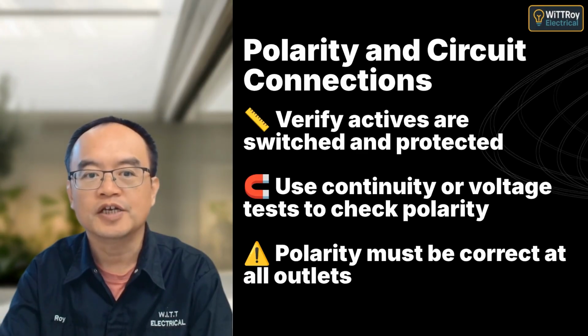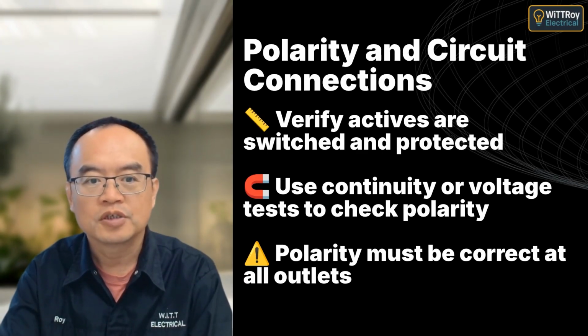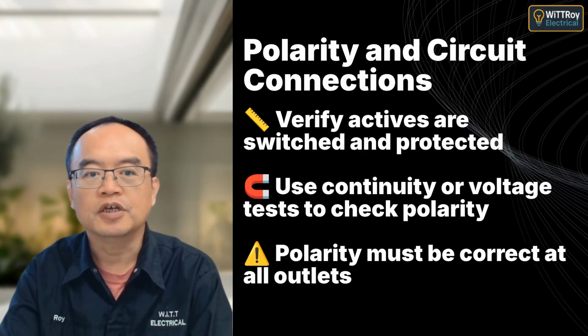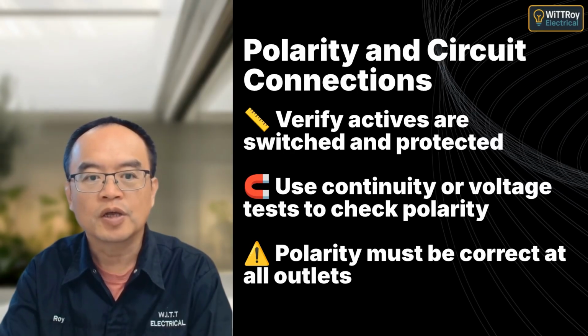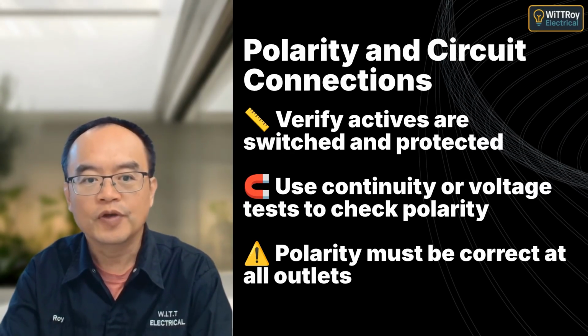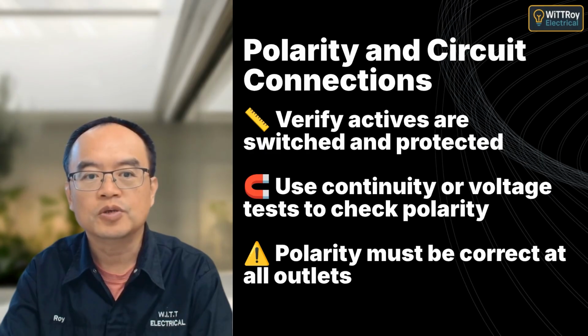Polarity testing ensures actives are correctly switched and fused, and that neutrals are not switched. Clause 4.6 outlines the correct methods and required outcomes. Verify polarity at all accessible points, including socket outlets.